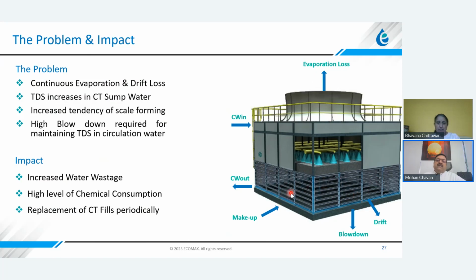And as this water is getting circulated in the condenser, there is an apparent tendency of scale formation in the condensers and in the pipes as well, and also the cooling tower fills. And then we need to add makeup water, because there is evaporation, and also because we have to maintain certain TDS levels or conductivity levels in the cooling towers. There is a blowdown that is happening. Sometimes it is continuous, sometimes it is intermittent.